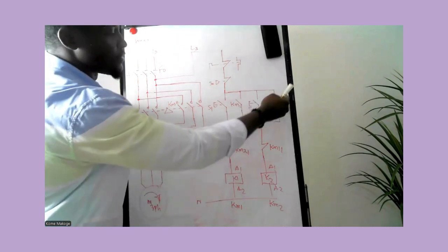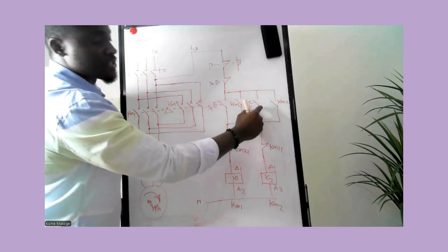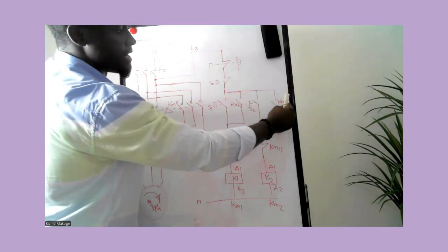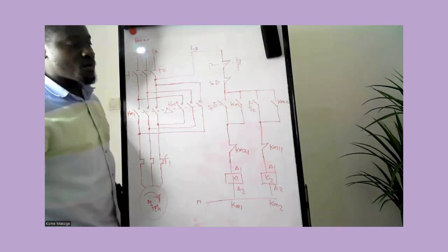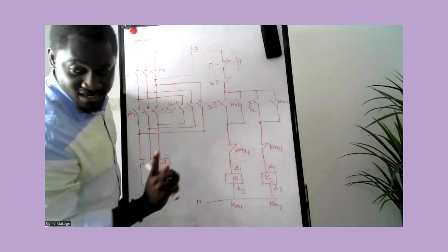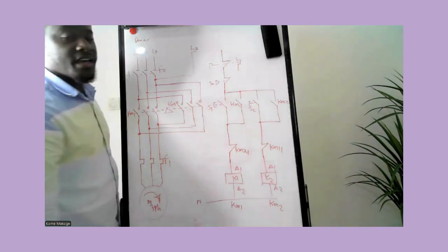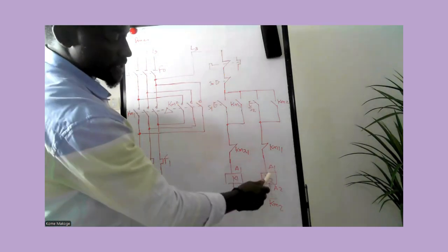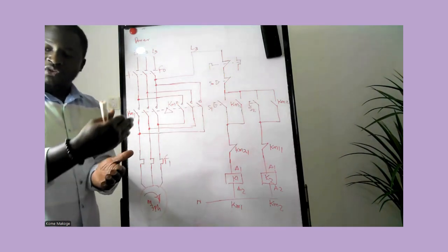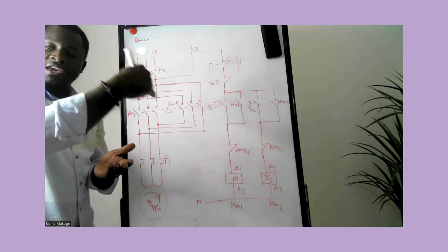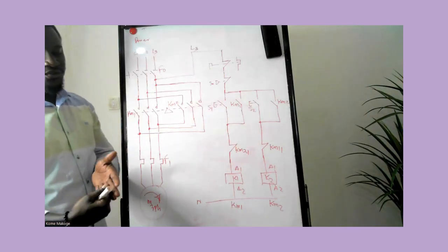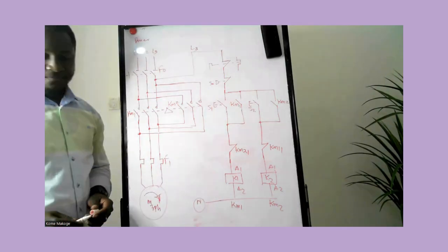Moving down, this is a coil A1 and A2, K1. Moving to the other side, S2 is an open contact representing the start push button of contactor KM1. Next on our right is KM2, an open contact of the contactor. Moving straight down we have KM11, which is a close contact of KM1. We also have the coil of K2 or KM2. If you look at the side of the coil you see two contacts — A1 at the top where you connect your live contact, and A2 at the bottom where you connect the neutral.